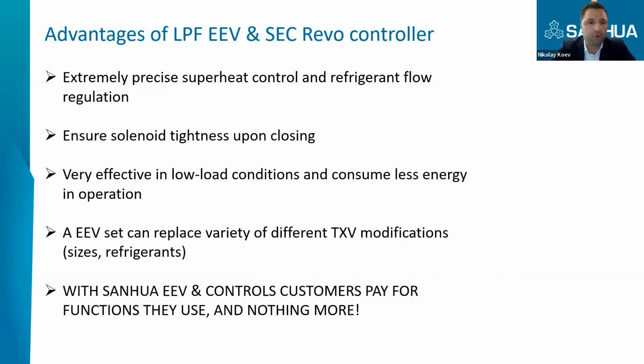What is important, especially for technicians who are used to dealing with different refrigerants and different capacities, if they used to work with thermostatic expansion valves, especially now that we see a lot of refrigerants on the market, I can say that the EEV is a universal solution. You can use the electronic expansion valve with any kind of refrigerant, and the capacity of one electronic expansion valve is much wider compared to thermostatic expansion valves. So one EEV set can replace, I would say, dozens of different thermostatic expansion valves, which means that you can really reduce the inventory of thermostatic expansion valves.